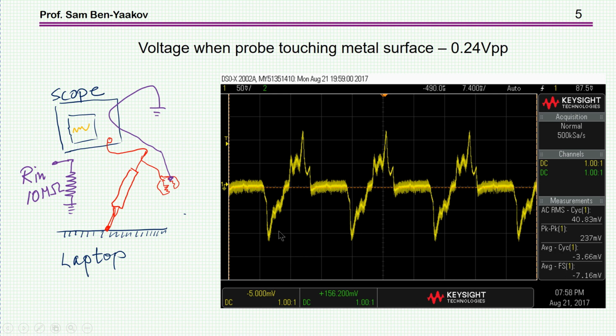What we see here is 50 hertz spikes, positive and negative. This is a result of the remnant signal due to the bridge rectifier of the converter. We see voltages up and down — this is when the diodes are conducting and the bus is reaching the input voltage. We see it plus minus, not like 0 and plus as shown before, because we're going through a capacitor and the DC level is filtered out, leaving the AC component, which is plus minus. The signal level isn't that much.